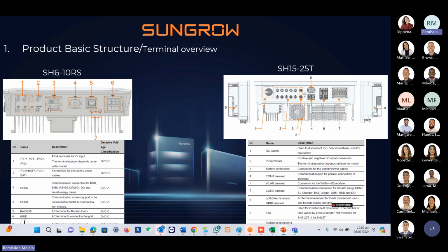On COM2, which is portion number 3, that's where we do our CAN and RS485 communication. So you need the meter to be able to communicate with the inverter, and you need the battery to communicate with this inverter via CAN. You can use the small green connector or a straight RJ45 for the CAN communication, but for the RS485 you only use A and B, and that's on the green connector block.